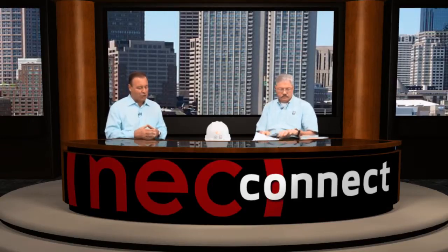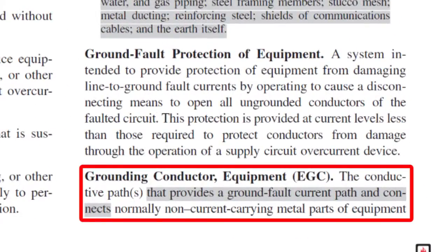More definitions about grounding and bonding. EGC — the term EGC stands for Equipment Grounding Conductor. That's a conductive path that's installed to connect normally non-current carrying parts of metal and equipment to the system grounded conductor or to the grounding electrode conductor or both. And it's important that the equipment grounding conductor also serves as a bonding conductor to interconnect non-current carrying metal parts of equipment.